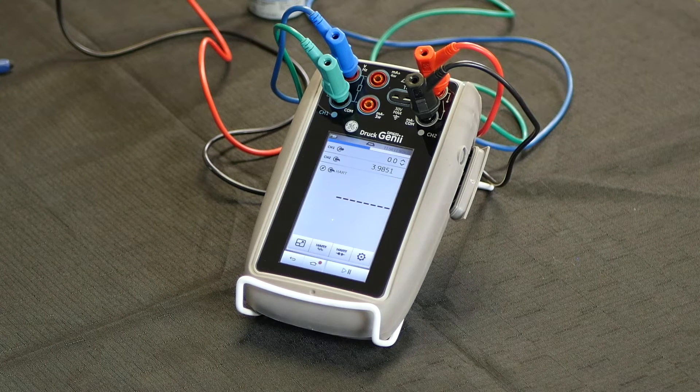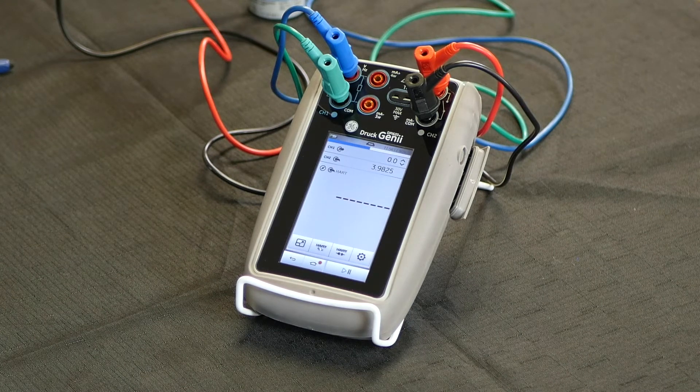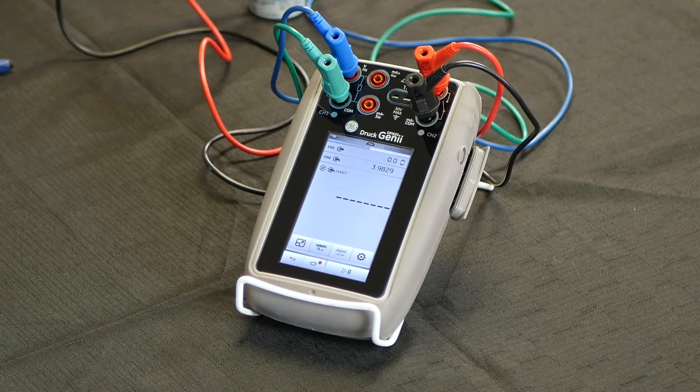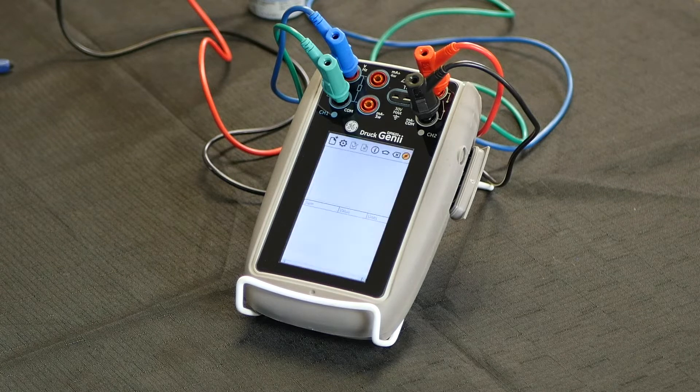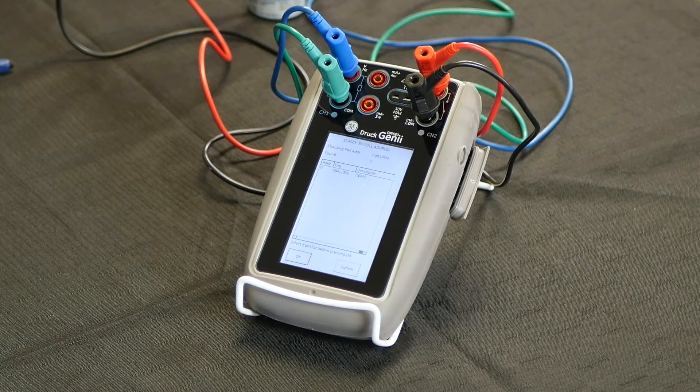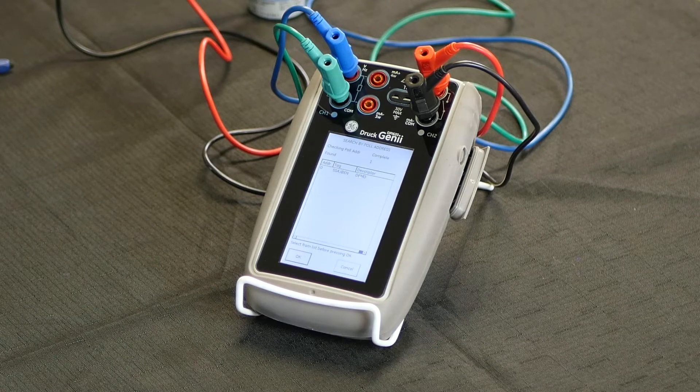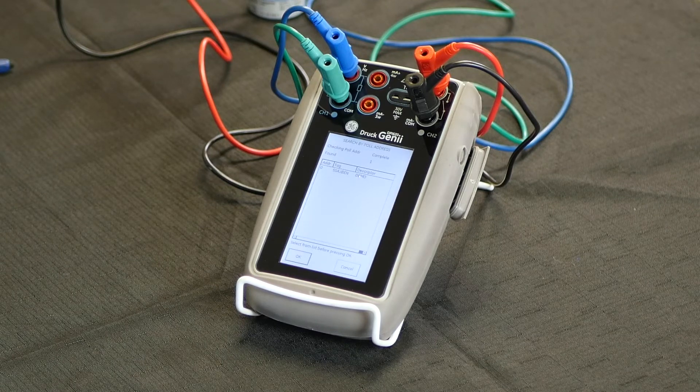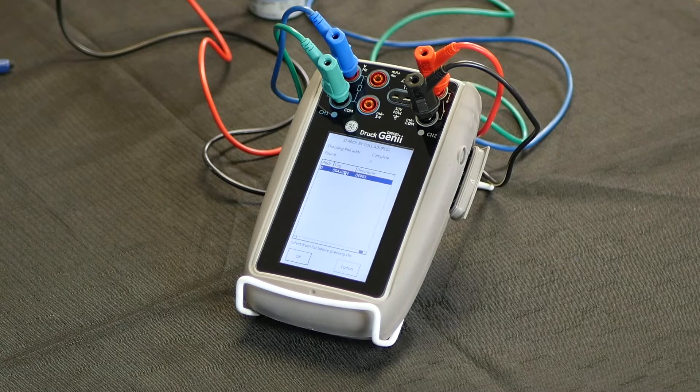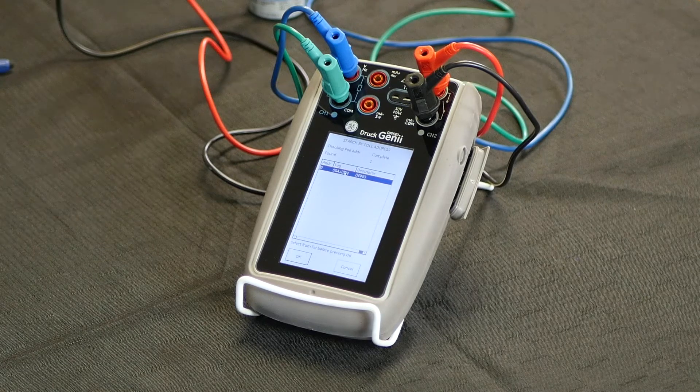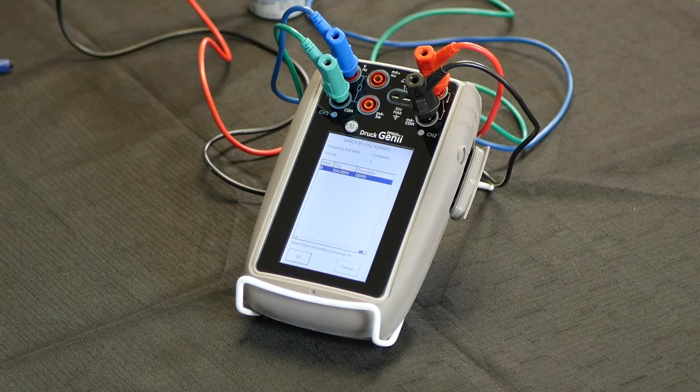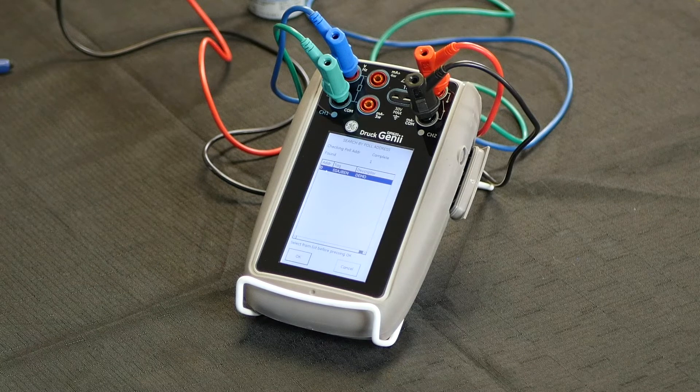Now I'm going to go into the online functionality of the communicator by clicking this button here. And the DPI 620 will go looking for HART devices on the loop. We currently only have one, so it's showing our unit. If there were multiple units on the loop, they would be displayed in a list here with their corresponding address number.